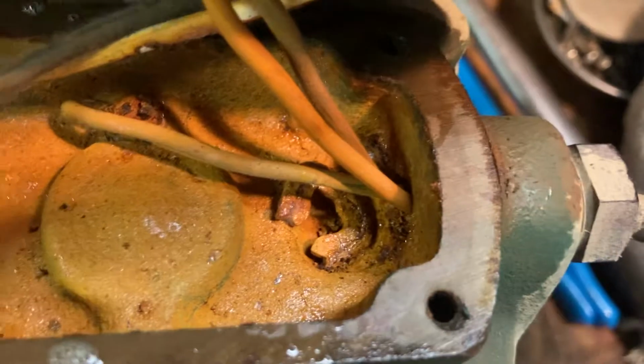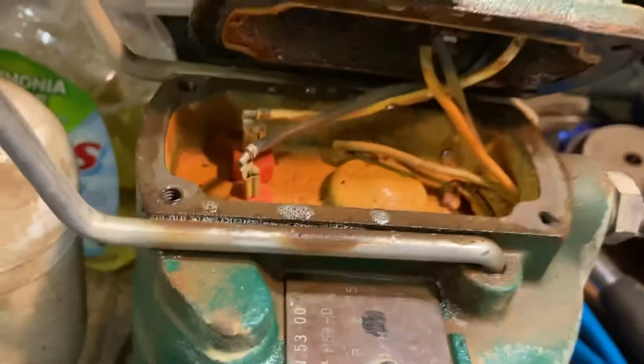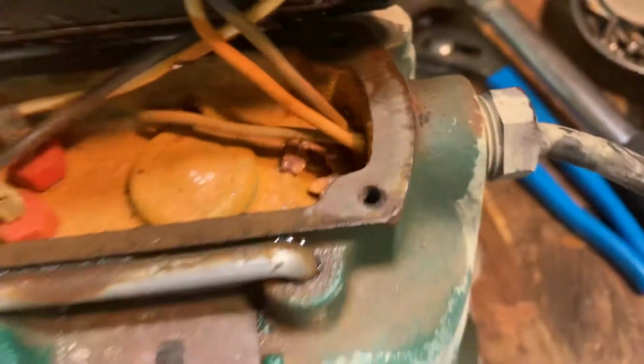Looks like there is some type of... I don't know if you can see that. That looks like some type of grommet that used to live around those entry wires, those service wires. All right. Maybe that's a clue, folks. Maybe that's a clue as to why these pumps are failing, right? Maybe it's not this gasket. Maybe it's this. Sorry about that, bro.